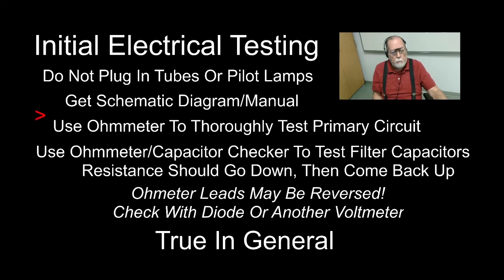And what you want to do is take your ohm meter and test the primary circuit. You want to test continuity from each blade of the 120 volt plug through the circuit inside, through the fuse, up to the transformer, through the on-off switch or the function switch, and so on and so forth, and make sure that there's continuity there, and make sure that there aren't any shorts or anything like that, okay? If you measure between a blade of the 110 plug and the chassis, there should be no resistance there, okay?